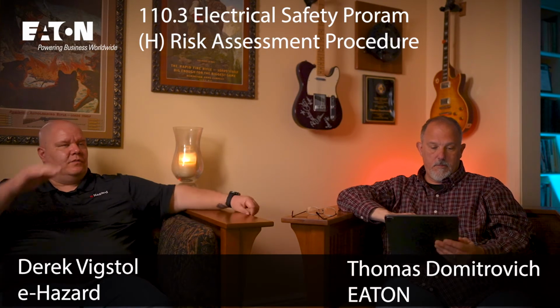The way I talk about this, and this procedure also helps with the arc flash risk assessment too, is that with shock it's easier, because it's basically around the question: do I have exposed parts or not? They define in 70E exposed as being capable of inadvertent contact or approach near in a safe distance by a person, and it's not suitably guarded, isolated, or insulated. And as a qualified person, we should be able to answer whether I have exposed circuit parts and conductors operating at above 50 volts, because that's really where my shock hazard is going to start. And then I go from there.